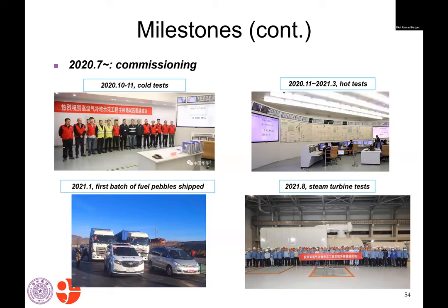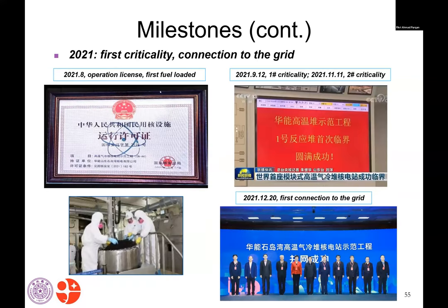After everything was installed, we started commissioning, which we divided into different phases. We started with cold tests first, because we wanted to make sure the leak rate of the reactor was low, and that the pressure boundary of the tubes and vessels were good. After that, we started the hot test, putting commissioning at a higher temperature, for example 250 degrees or higher, to make sure everything was good again. After that, we had to test the steam turbine, to make sure everything for electricity generation was good.